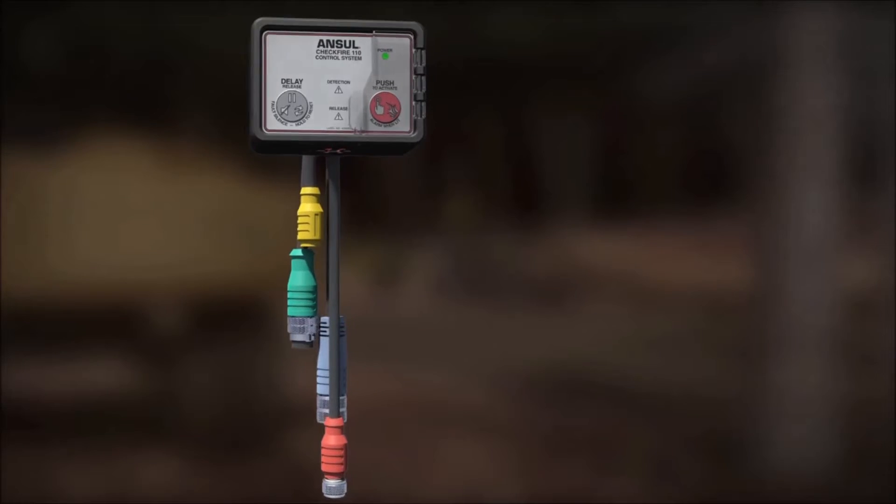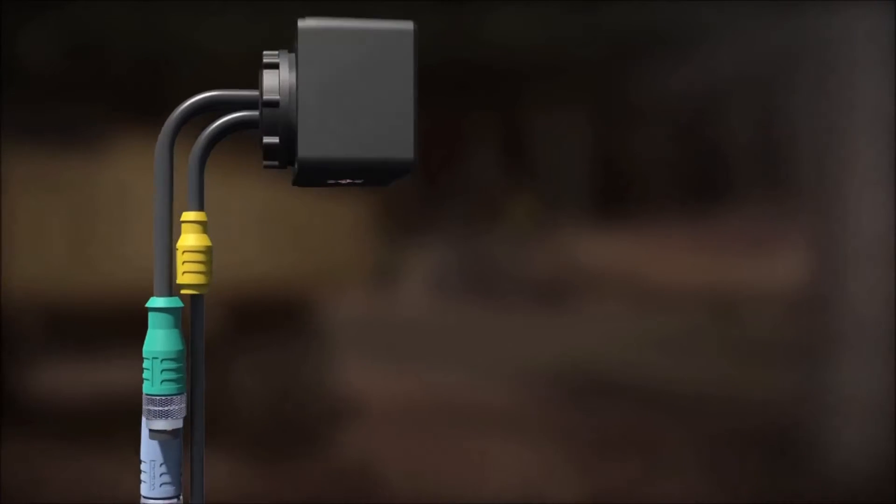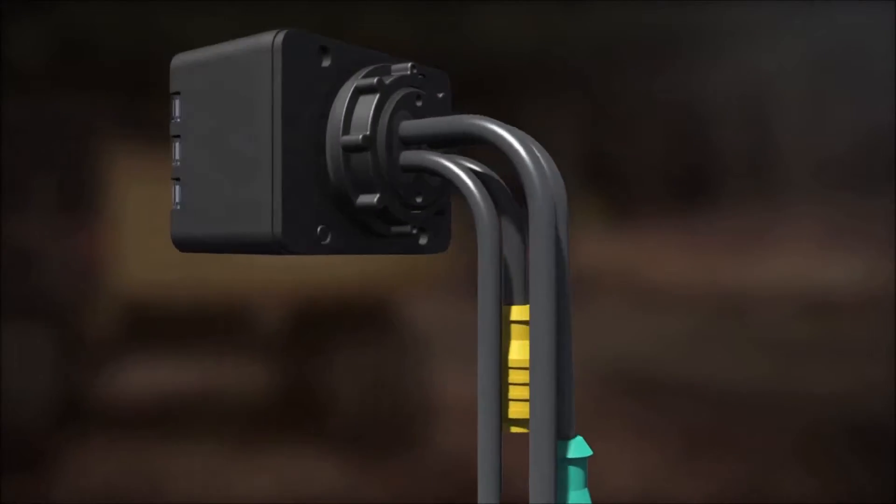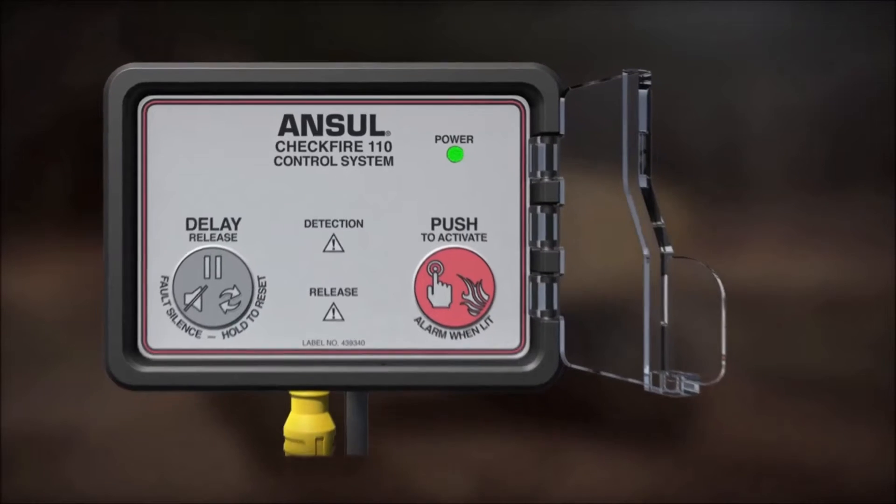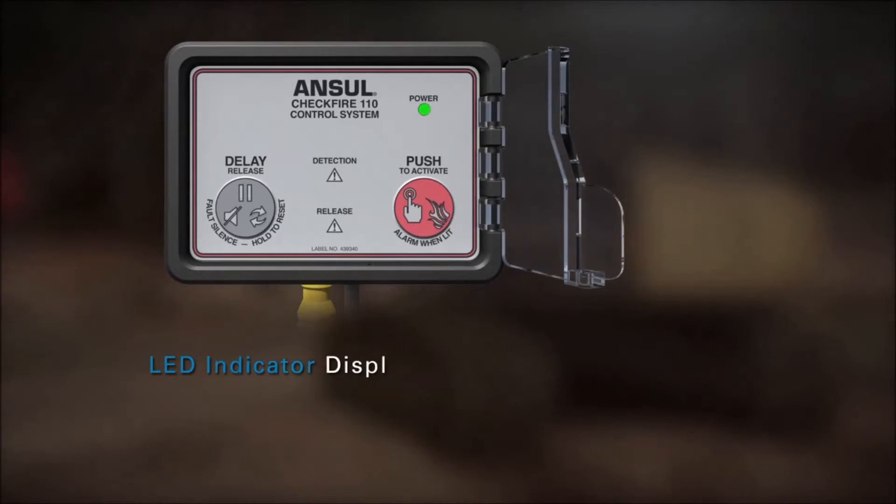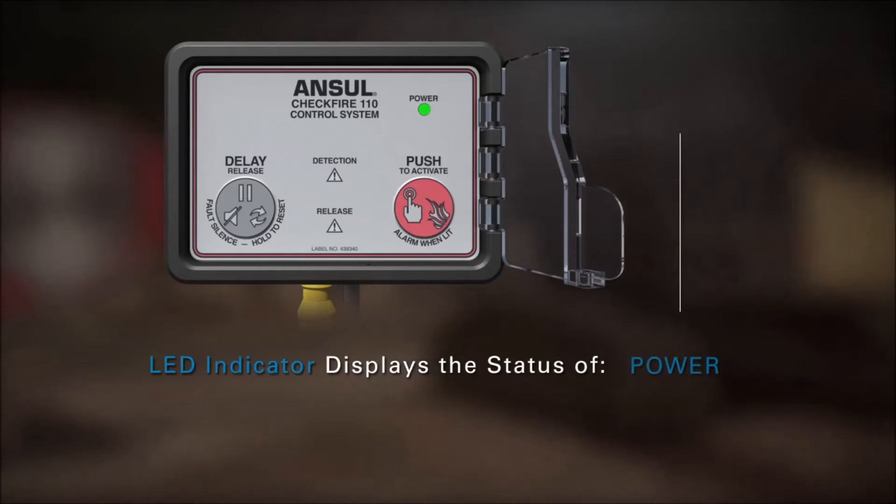The CheckFire 110 control module processes both input and output signals and controls the sequence of critical actions. LED indicators provide notification of system status relating to power, release, and detection.